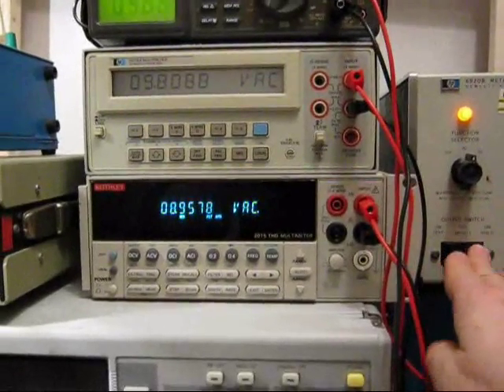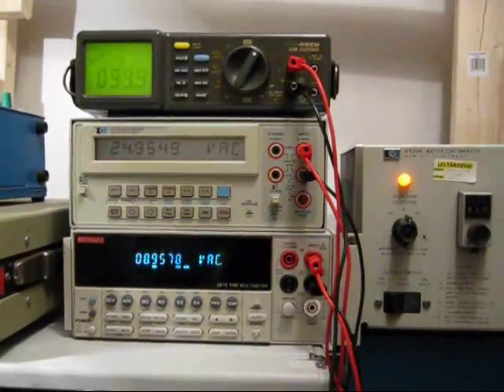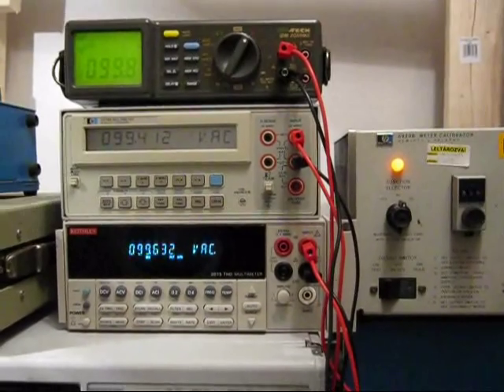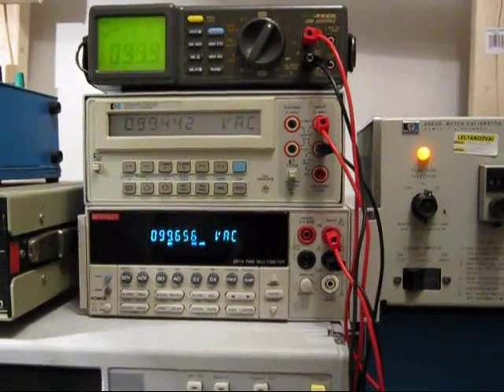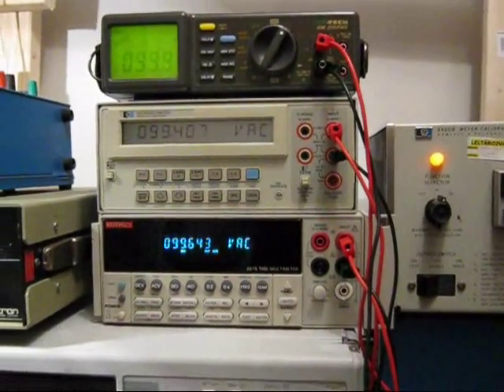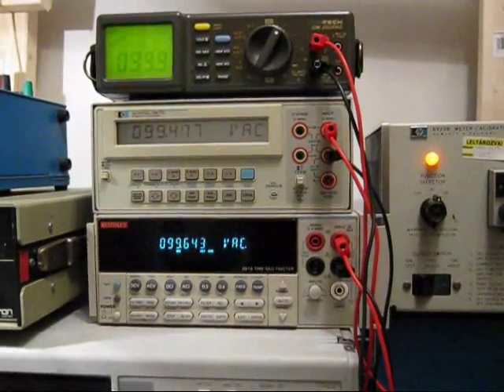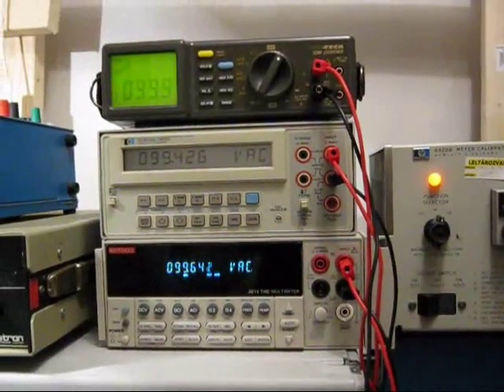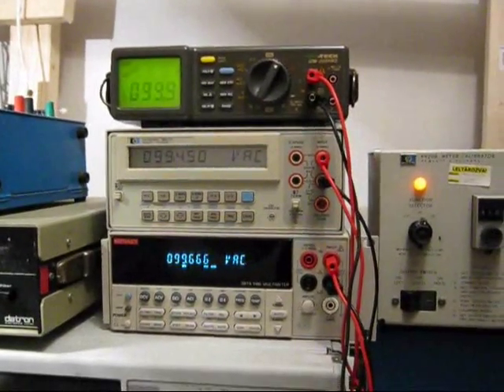And going up a range on the calibrator, and just reset the output. And we've got 99.6 on the Keithley, 99.4 on the HP and 99.9 on the Isotec.